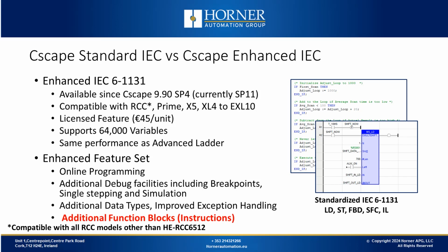Enhanced IEC supports 64,000 variables, compared to the 10,000 that Standard IEC supports. Enhanced IEC also has the same performance and execution rate as Advanced Ladder. Additional features of Enhanced IEC include online programming, which Standard IEC does not support. This allows you to make logic changes in your controller without stopping the controller.